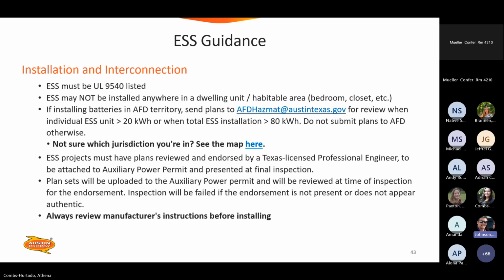And then for ESS, because we do get different manufacturers, there are all kinds of different installation methods for what you're trying to do. There's always new technology coming out too. Always, always, always review the manufacturer's instructions before installing. They could tell you conductor sizing, clearances, locations. They won't tell you anything about how we install per our interconnect guide, but they will tell you, for that particular piece of equipment, all that they have about it. Next slide, please.